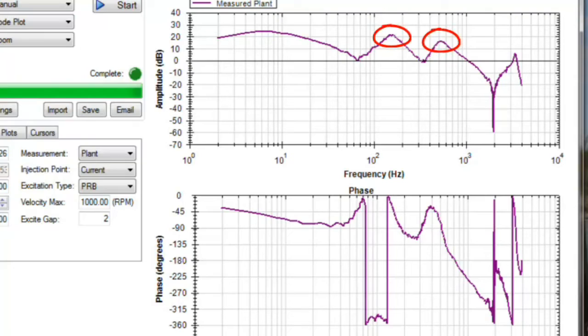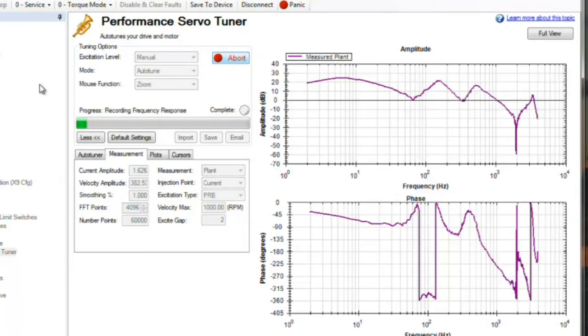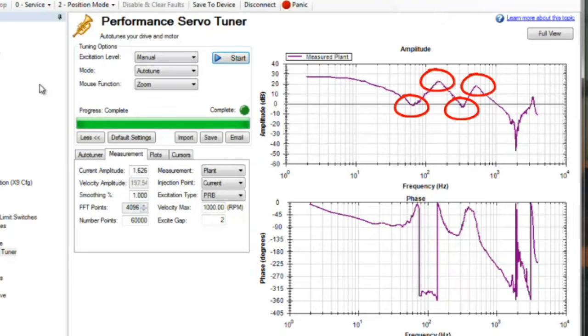At this point, an auto-tune will be performed on the system. The current can be set automatically or manually and injected into the current loop. The excitation is PRB or pseudo-random binary. It should be noticed that the Bode plot does not change after tuning, since tuning has no effect on the mechanics or the plant plot.